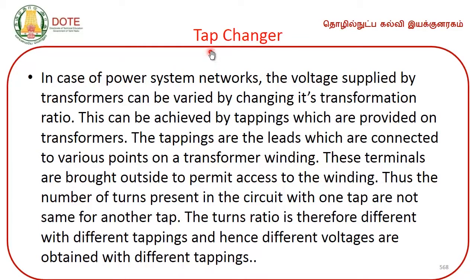Now, let us move on to the tap changer arrangement. In case of power system networks, the voltage supplied by the transformers can be varied by changing its transformation ratio. This can be achieved by tappings which are provided on the transformers. The tappings are the leads which are connected to various points on a transformer winding. These terminals are brought outside to permit access to the windings.